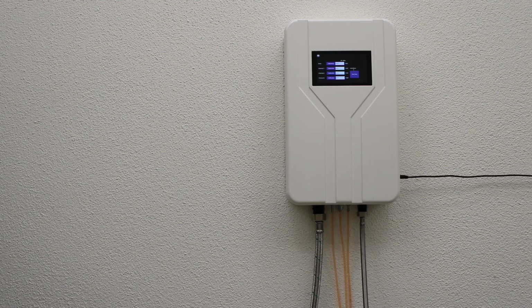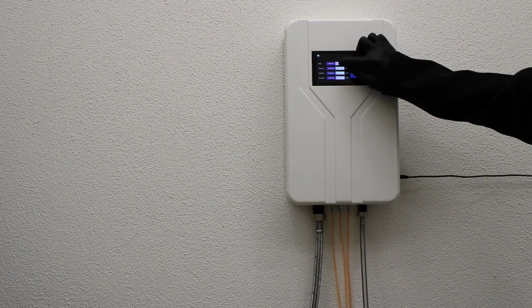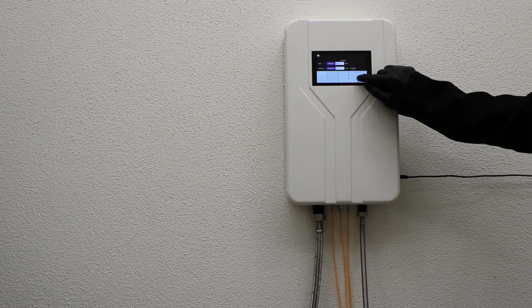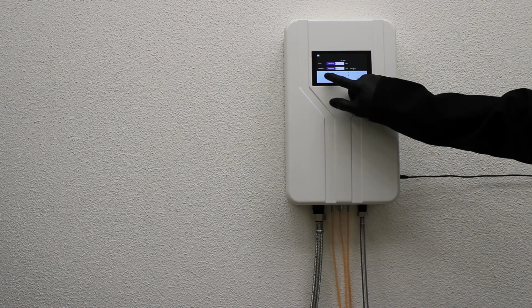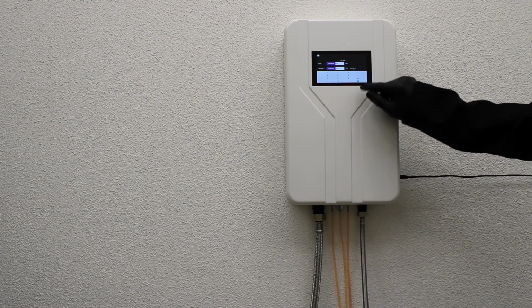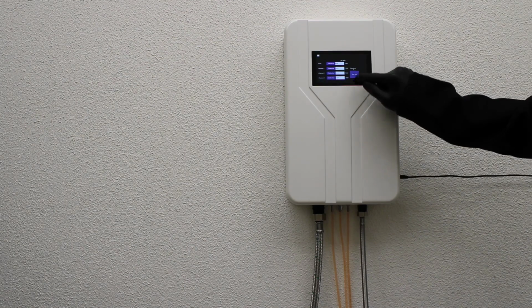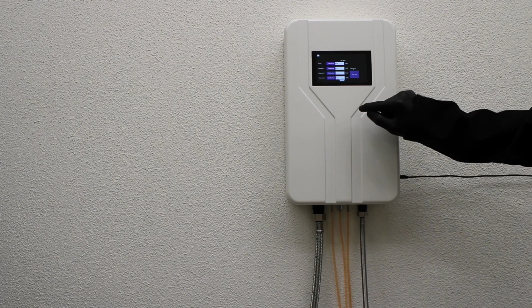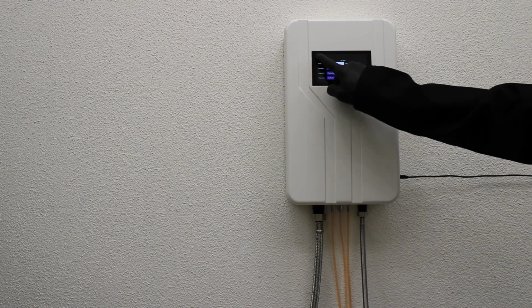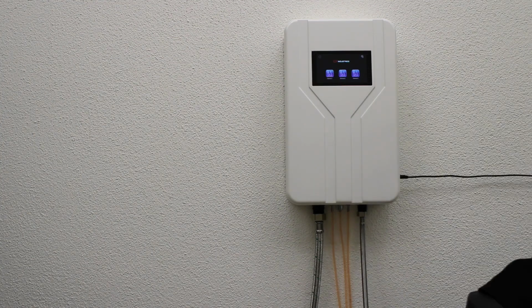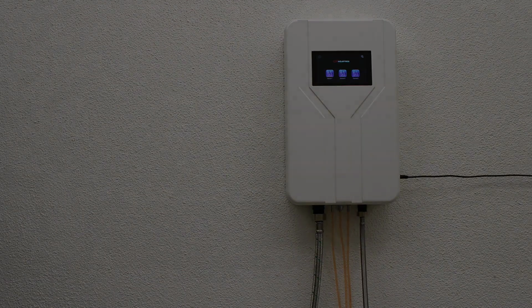To do this, go back to the device. Next to Calibrate in the Water section, there is a white input field. Press the white field, and a keyboard will appear on the screen. Enter the measured water volume. Once you have done this, press the Next button at the bottom right of the keyboard to proceed until the keyboard disappears. Then press the Save Data button located on the right side of the screen. The water calibration is now complete. If you do not wish to calibrate anything further, you can return to the menu using the back button at the top left corner. Pressing the back button again will return you to the main user interface.